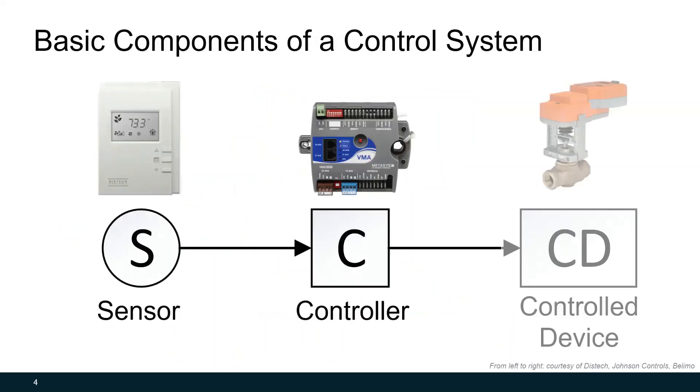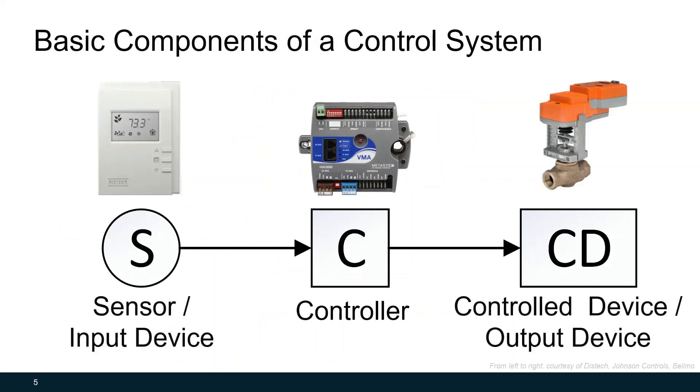Like I stated before, the basic components of a control system are the sensor, the controller, and the control device. The sensor is sometimes called the input device and the control device is sometimes called the output device. This is because the sensor sends an input signal into the controller and the controller sends an output signal to the control device. The terminology around the signals input and output can be confusing. Just remember that the signal is labeled in its relation to the controller. Inputs go into the controller and outputs go out of the controller.